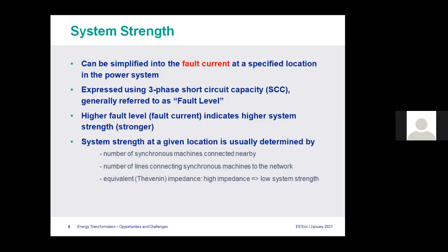And yeah, this is just some description about system strength. Now, this term, I don't know whether it's widely used in Sri Lanka these days. It's normally related to fault current. And we all know fault current is normally the three-phase short circuit capacity, which is referred to as fault level. Then if the fault level at a particular location is high, we call it a stronger system or stronger location from a system strength point of view.